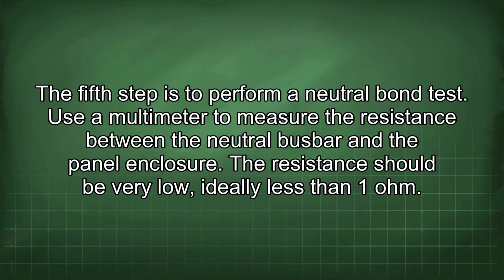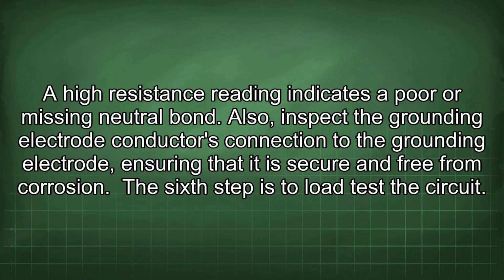The fifth step is to perform a neutral bond test. Use a multimeter to measure the resistance between the neutral busbar and the panel enclosure. The resistance should be very low, ideally less than 1 ohm. A high resistance reading indicates a poor or missing neutral bond. Also, inspect the grounding electrode conductor's connection to the grounding electrode, ensuring that it is secure and free from corrosion.